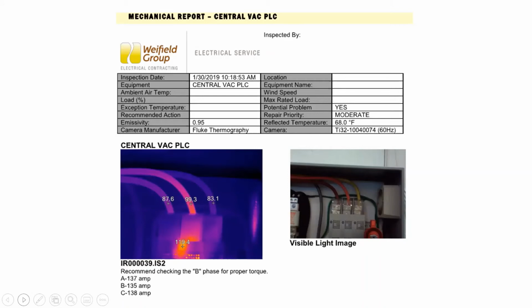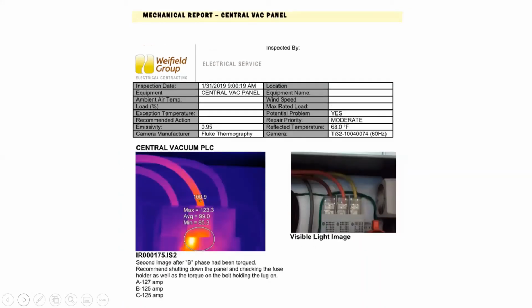It says recommend checking B phase for proper torque. This is the second image after B phase had been torqued. Somebody had torqued it down, and it recommends shutting down the panel and checking the fuse holder as well as the torque on the bolt holding the lug on.